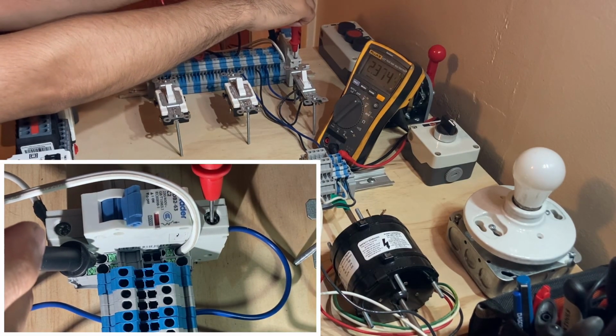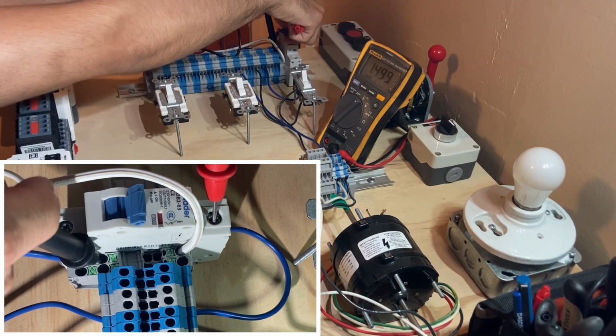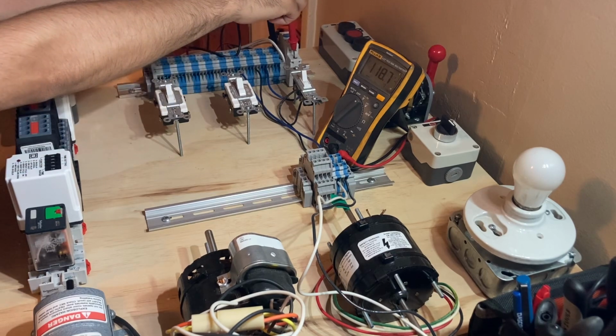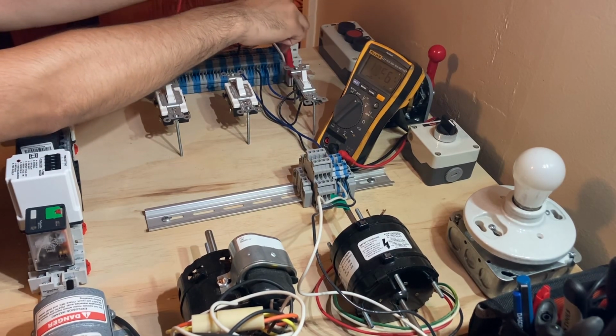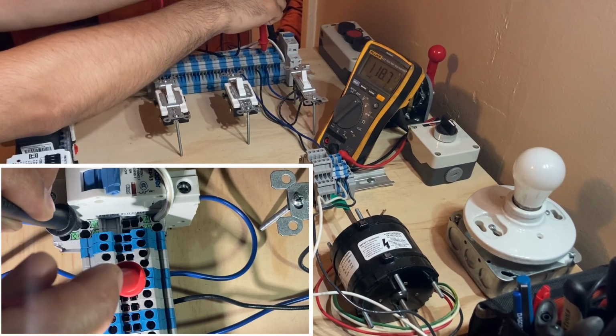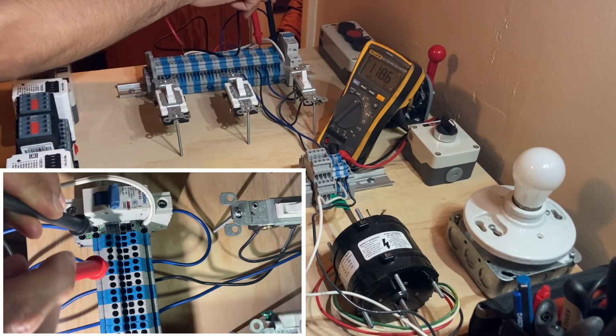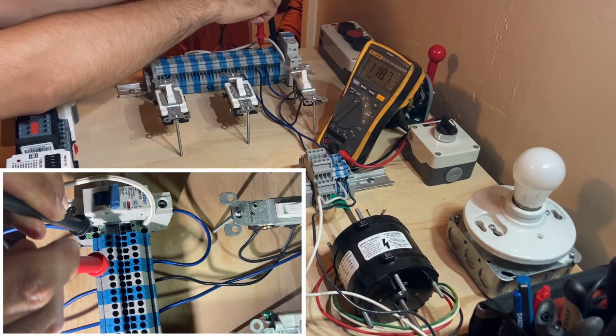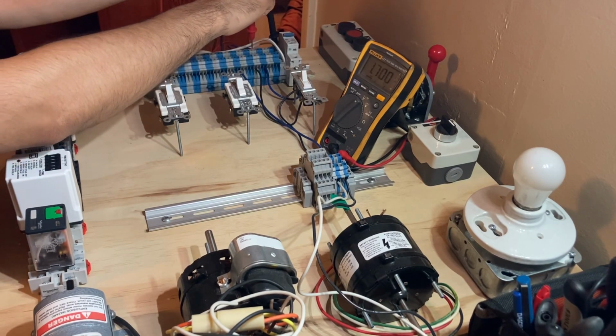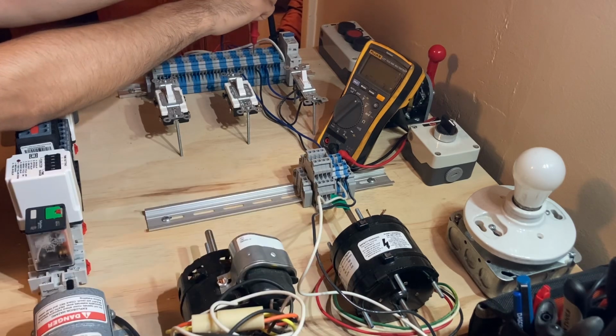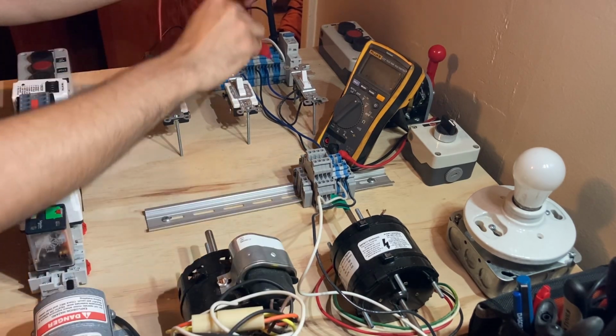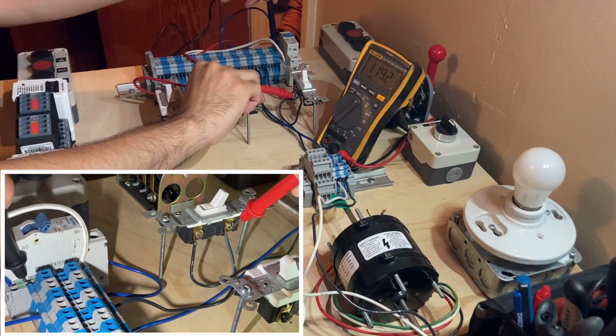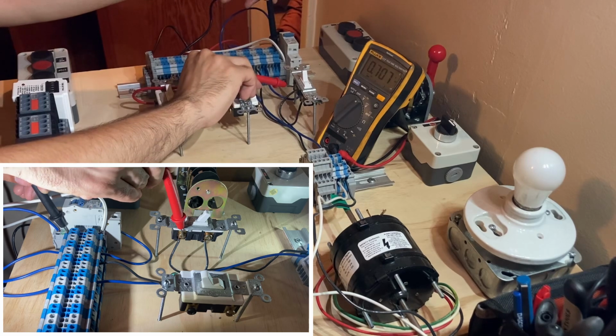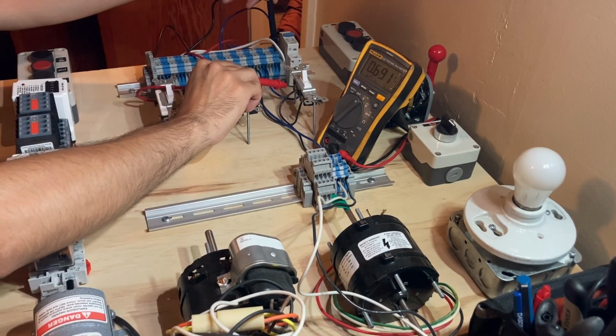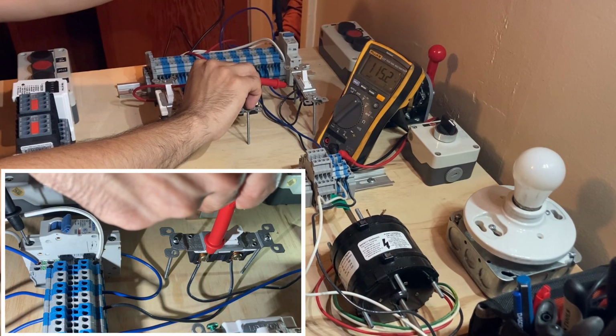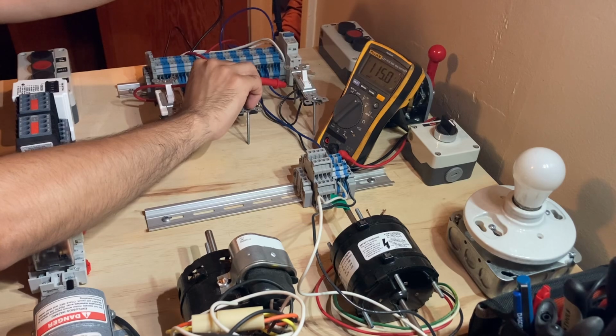Now leaving my black lead on my neutral, I'm going to continue the path and follow the voltage. I turn my breaker on and I'm getting voltage now across my breaker. Voltage is continuing along the terminal blocks, getting 118 all the way. On the line side of my light switch, and I have 0 volts on the load side, meaning this switch is off. Switching my black lead now to my line side, you see that now I have voltage there.